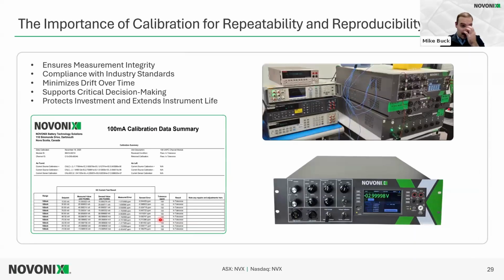Next slide. I want to touch a little bit on calibration and how it plays into repeatability and reproducibility. Repeatability is the ability to repeat a measurement, and reproducibility is taking that instrument and, unbiased, setting it up in another location and being able to repeat the same outputs that we were able to produce in our labs. For calibration, we spend a lot of time with many different meters and high precision tools to verify our methods and make sure that we follow tight industry compliances, and that we have lab processes and methods in place to minimize the amount of drift that the systems are going to have over time and maximize the quality of signal that the instrument has before it ever gets to the customer site.